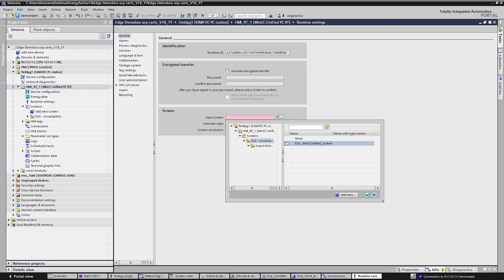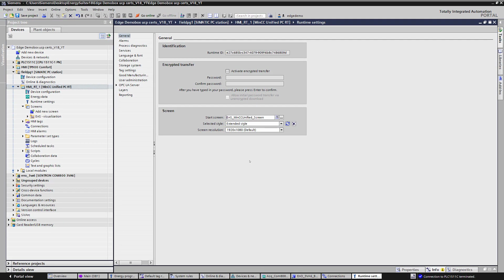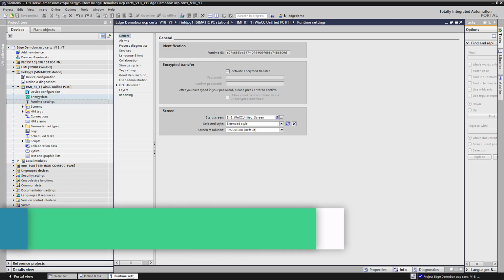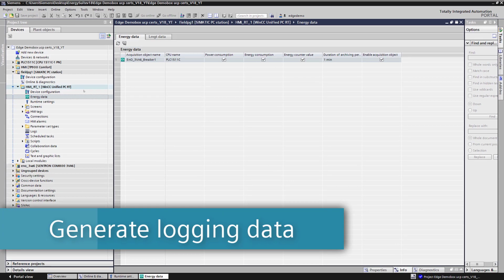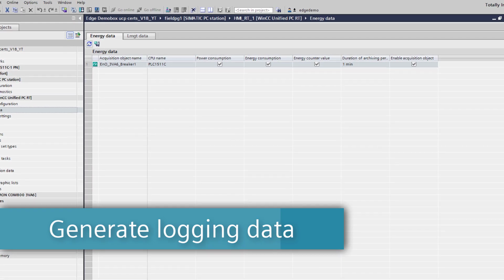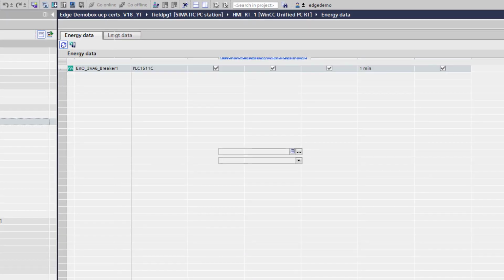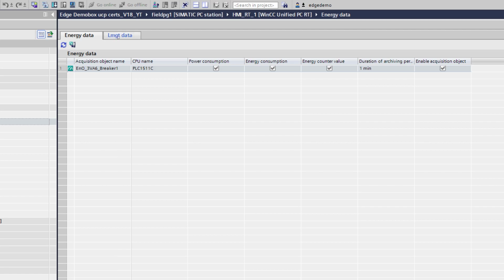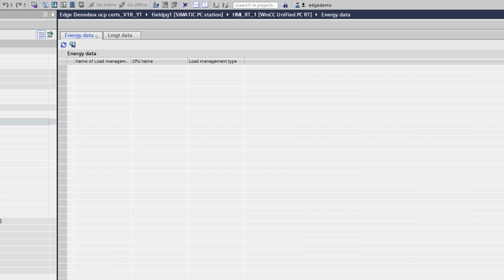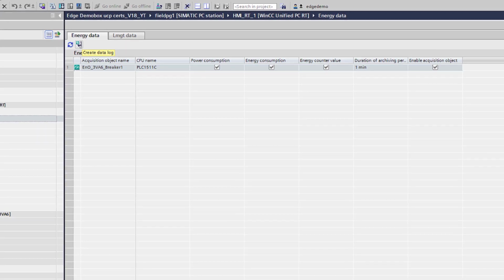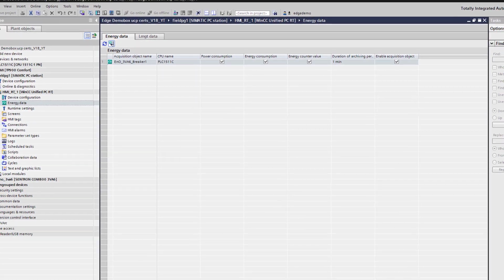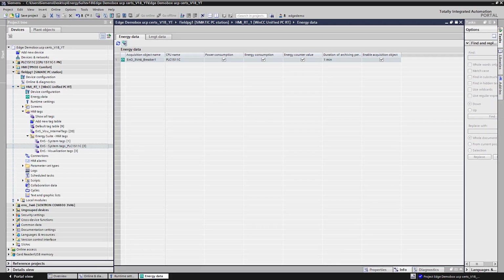Alright, once we've selected WinCC Unified Screen of Choice, we can now talk about how we log data using the tool. Hit the refresh button to make sure everything's up to date. And if we had any actors, they would show up in this field, but we don't. We're going to hit Create Data Log, and then it will auto-generate the data log for us as well. Notice it opened and expanded some HMI tags. But if we check the log setting, which we'll do in a second, first we'll check the HMI tags.